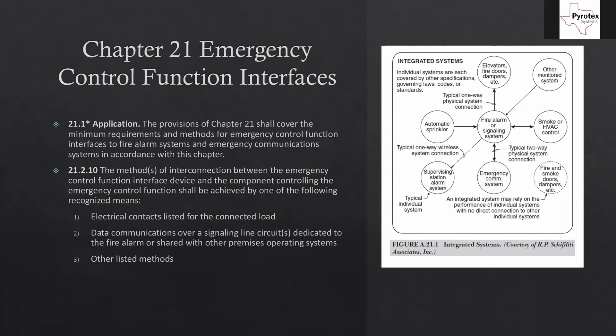The methods of interconnection between the emergency control function interface device and the component controlling the emergency control function shall be achieved by one of the following recognized means: electrical contacts listed for the connected load — that would be like a control relay used for dampers, elevator recall, or air handler shutdown; data communication over a signaling line circuit dedicated to the fire alarm or shared with other premises operating systems — that's how we communicate with the ECS system; or other listed methods. Most of these are going to be covered by one or two.